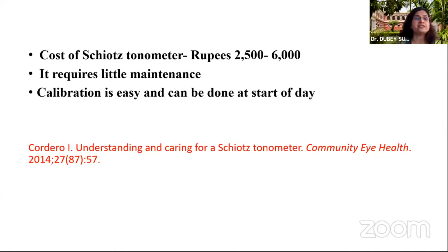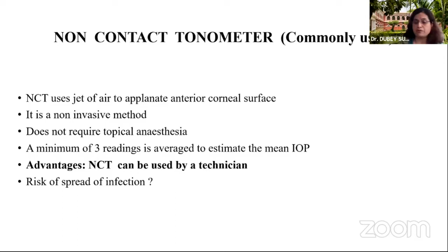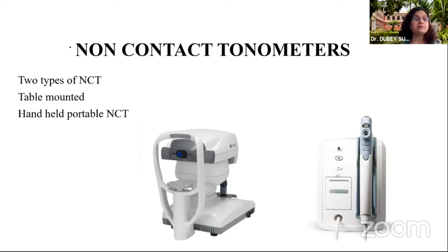Amongst general ophthalmologists, non-contact tonometer is the most commonly used tonometer, and it uses a jet of air to applanate the anterior corneal surface. It's a non-invasive method, does not require topical anesthesia, and a minimum of 3 readings are averaged to estimate the mean IOP. So the biggest advantage is that it can be used by a technician. I'm going to discuss the aerosol generation with this particular procedure, and it is available as table mounted or handheld portable. So it is reliable within normal range, and that is why it is useful for screening purposes.